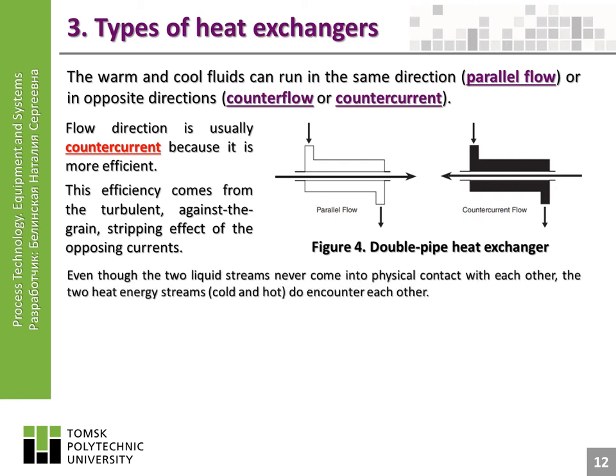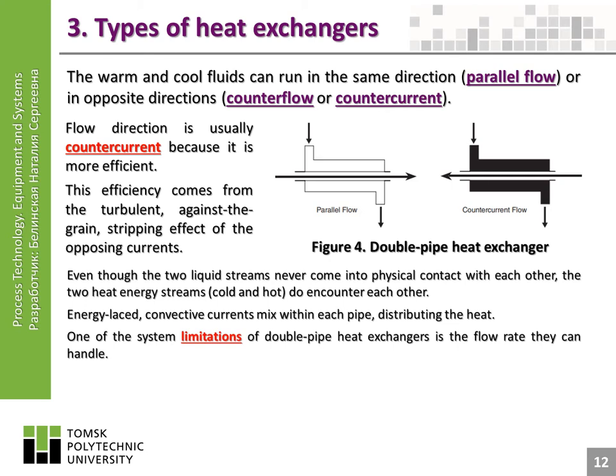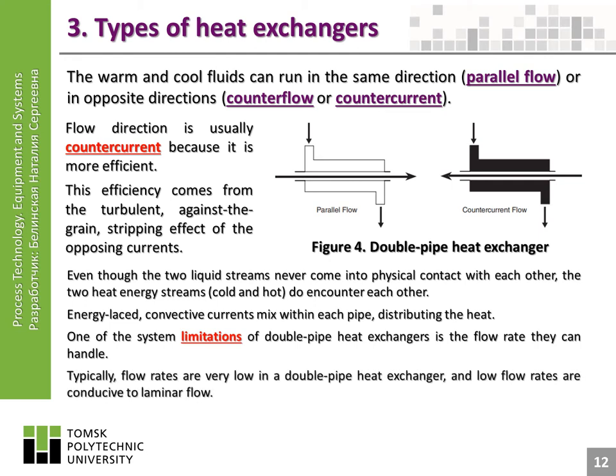Even though the two liquid streams never come into physical contact with each other, the two heat energy streams — cold and hot — do encounter each other. Energy-laced convective currents mix within each pipe, distributing the heat. One of the system limitations of double pipe heat exchangers is the flow rate they can handle. Typically, flow rates are very low in a double pipe heat exchanger, and low flow rates are conducive to laminar flow.